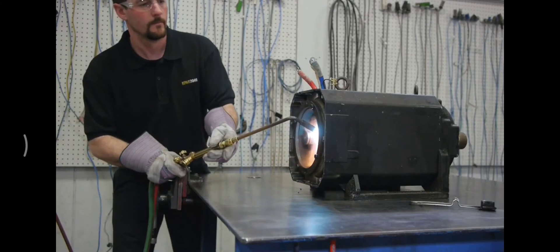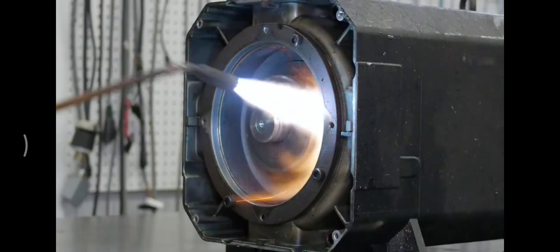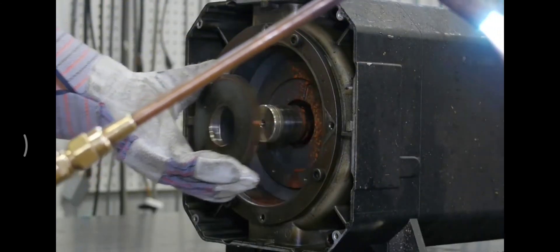We then remove the speed sensor wheel by applying heat along with the opposite pulley end bell.